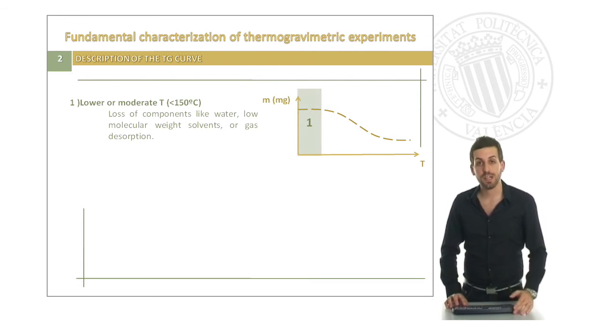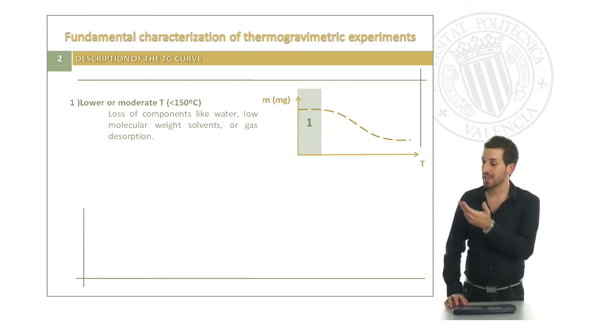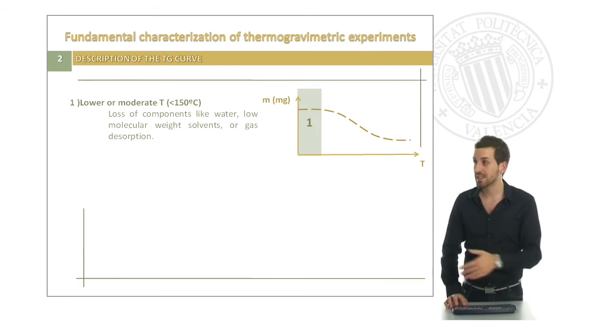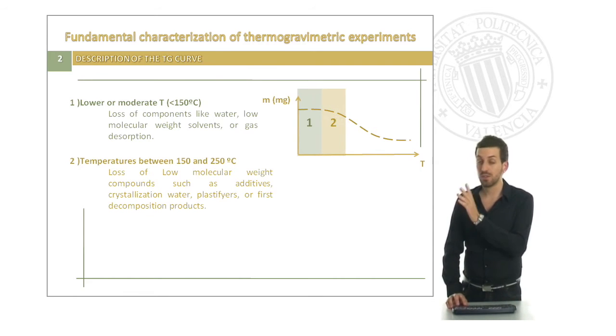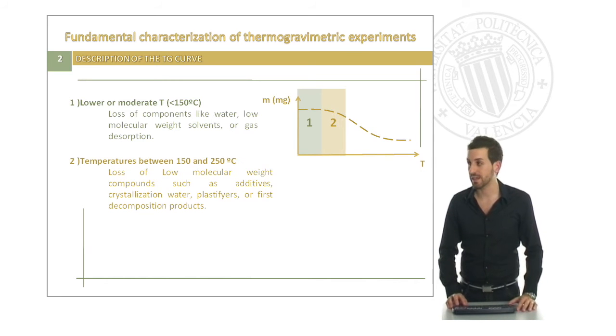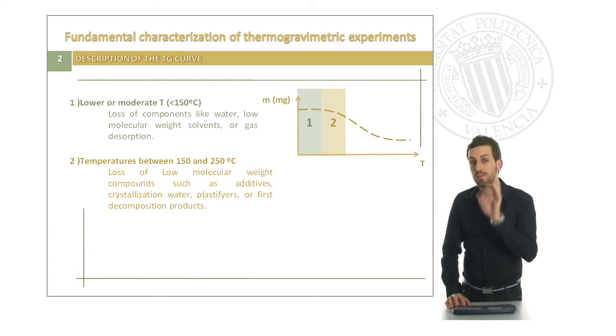In the increasing temperature axis, we can see as in the lower or moderate temperature range, so below 150 degrees, we will be able to see the loss of components like water, low molecular weight solvents or gas desorption. If we increase this temperature between 150 and 250 Celsius degrees, we will be able to see the loss of low molecular weight compounds such as different additives, crystallization water, plasticizers or first decomposition products of our polymer.